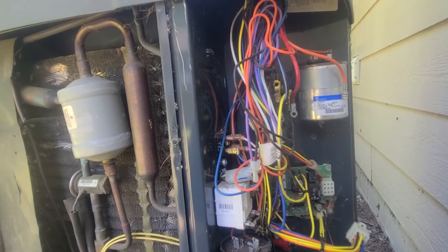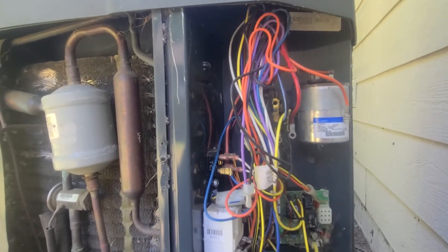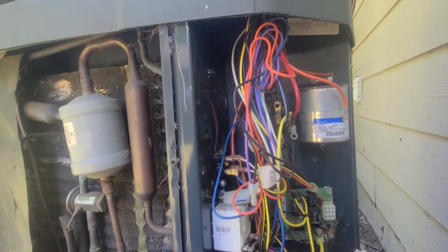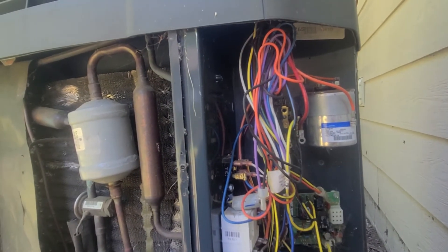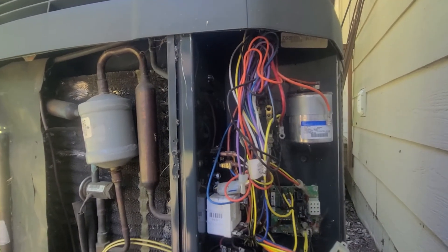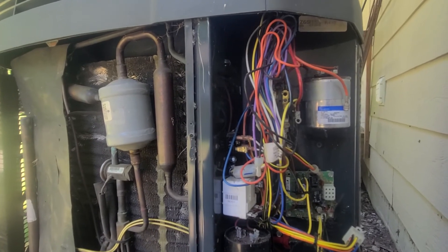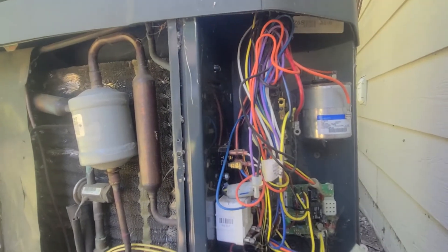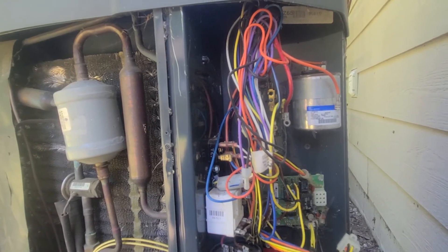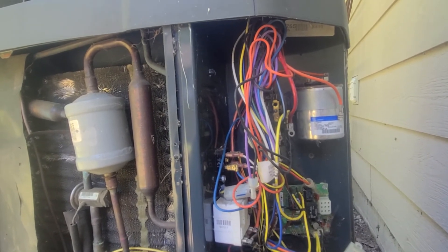It's getting into that ballpark of its lifespan. Pretty simple, quick diagnostics. If they do go the compressor route, I'm going to replace the compressor and all the start components — run capacitors, contactors, all of that — along with the filter dryer and everything at once.